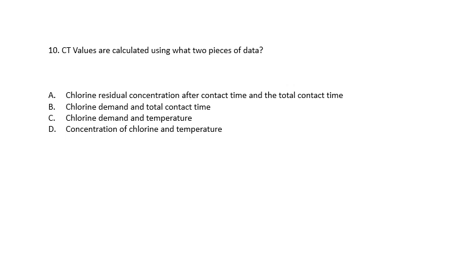Question 10. CT values are calculated using what two pieces of data? Chlorine residual concentration after contact time and the total contact time, chlorine demand and total contact time, chlorine demand and temperature, or the concentration of chlorine and temperature. CT values are calculated by the chlorine residual concentration after the contact time and total contact time.